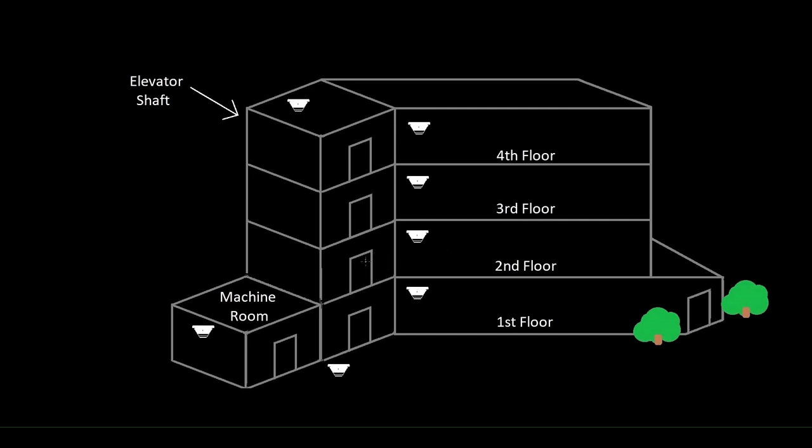We don't have the luxury now of turning on your fire hat relay and your alternate relay because they can only have one relay come on. So we'll give them a relay and we could label it machine room slash pit, but we're going to need another relay for the elevator shaft because when the top of shaft activates we're not sending the car to two, we're going to send it to one, and so that's an example of when you would need that fourth relay.